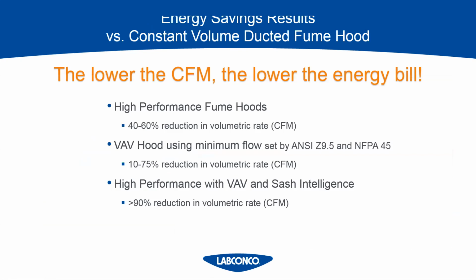So if you're looking to save this money and you're using a ducted hood, here's some other figures to help illustrate what decisions you can make in order to lower that annual bill. Just switching to a high performance hood can reduce your air consumption by 40 to 60%. So if you're on the market for a hood and you are going ducted, the amount of hoods that are offered today that are high performance is most of them, I would say, at least from Labconco. So I would definitely switch to a high performance hood if you're using that hood regularly.